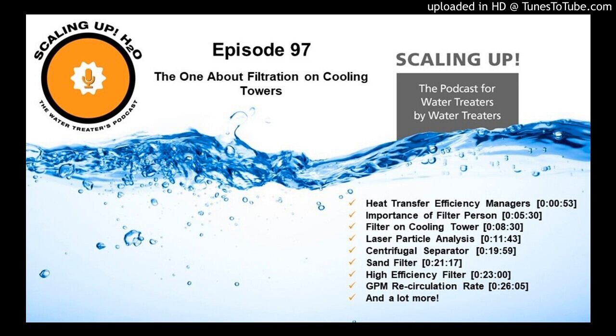Well, you bring up an interesting point. I know several times we've been invited to a cooling tower and install people just set it up the way it comes out of the box. And we had to dial in the correct backwash, whether it was on a time, which I don't like, or it was on pressure, which I do like more. And I'm hoping you'll talk about that.